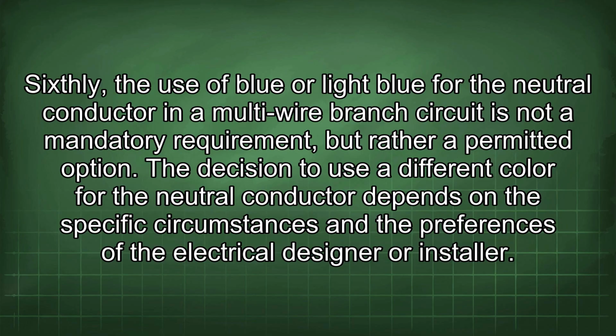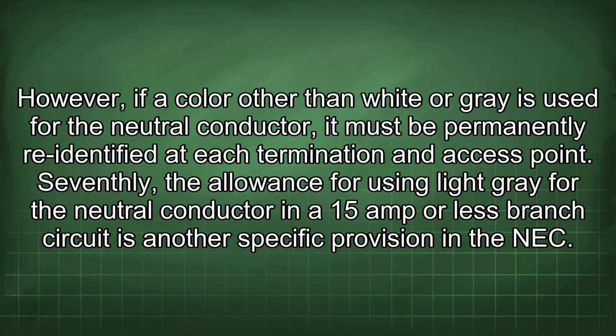Sixthly, the use of blue or light blue for the neutral conductor in a multi-wire branch circuit is not a mandatory requirement, but rather a permitted option. The decision to use a different color for the neutral conductor depends on the specific circumstances and the preferences of the electrical designer or installer. However, if a color other than white or gray is used for the neutral conductor, it must be permanently re-identified at each termination and access point.